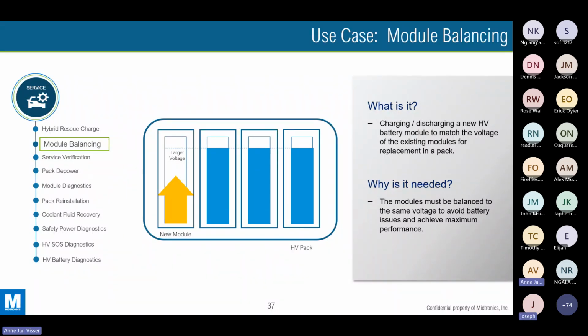If you replace a module with another one, usually the new module is not at the same state of charge level as the other modules still existing in the pack. The problem is that if the deviation is too big, the pack software, the BCU, will not accept the new module, and there will be a problem because the car won't drive due to an error in the battery pack. Therefore, module balancing is important to make sure the new module is at the same level as the other modules in the pack.